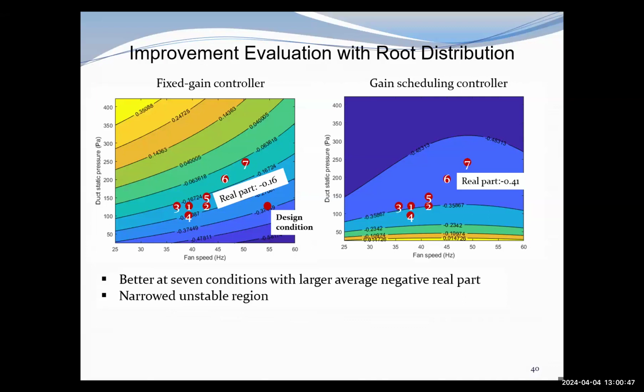I was wondering if you could explain why on the fixed gain controller it becomes more unstable as the duct static pressure increases, more positive, and it's the reverse, as duct static pressure decreases on the gain scheduling controller, it gets more unstable. So as the duct static pressure increases, the system is becoming more unstable. Actually, the fan duct gain is proportional to the ratio of duct static pressure over fan speed. The ratio will impact the system's performance. If the duct static pressure increases, then the fan duct gain will increase. The increased gain will make the system more aggressive. Okay, that makes sense.